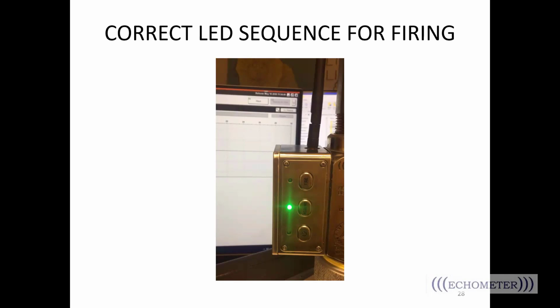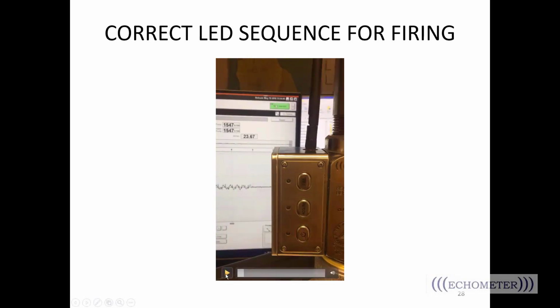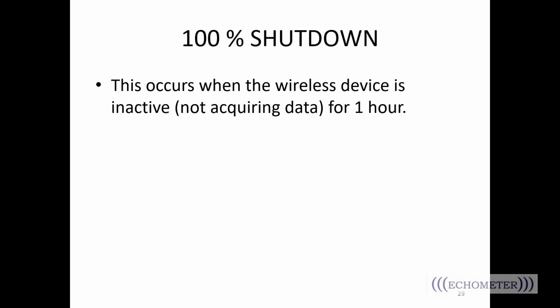All right, so if you click that Acquire button, or you click that Start New Test button, and that Acquire button starts flashing and the Fire button starts flashing, and you're waiting and it's been more than about 15, 16 seconds, then that's going to indicate you've got a problem. All right, so 100% shutdown occurs when your wireless sensor is inactive for 1 hour. That's just built in for the power save.